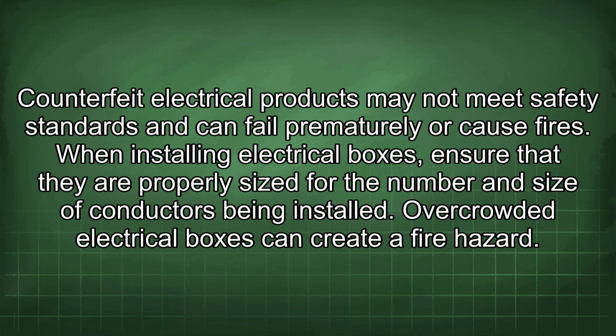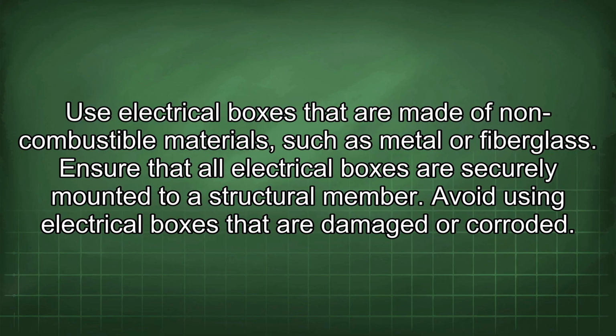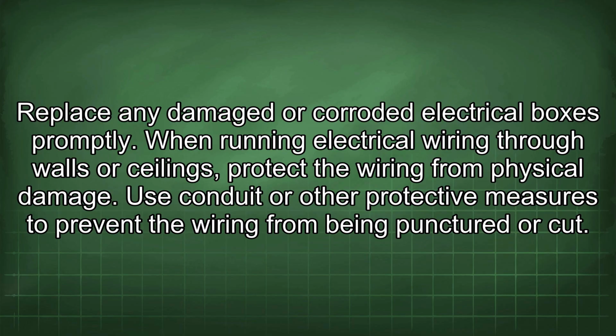When installing electrical boxes, ensure that they are properly sized for the number and size of conductors being installed. Overcrowded electrical boxes can create a fire hazard. Use electrical boxes that are made of non-combustible materials, such as metal or fiberglass. Ensure that all electrical boxes are securely mounted to a structural member. Avoid using electrical boxes that are damaged or corroded. Replace any damaged or corroded electrical boxes promptly.